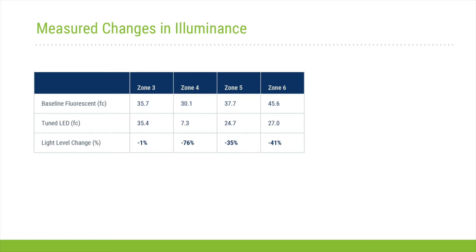Someone asked a great question here about light level tuning changing industry attitude towards ambient illumination, going from absolute foot candles to contrast ratios. Contrast is a very important thing to focus on. Illuminance is really just a snapshot, and it's an easy way to think about something. Contrast ratios are really how bright the visual appearance of the space is. You ideally want roughly a 3-to-1 contrast ratio, because your eye can't really see a difference beyond 3-to-1. And so it is important that when you are examining a scene, you're not thinking of just the one value. You're really examining the entire space.